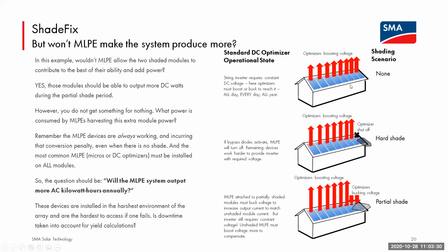So for non-shaded arrays, you would say, well, okay, Rob, I guess you've proved to me that traditional optimizers are not needed. But here you have a hard shaded situation. So in a hard shaded situation, that optimizer, again, cannot magically make power from a module that's not giving it any power. So this is showing that optimizer really shuts off. So there's no power from the module to power it up. So it bypasses over just like it would if it wasn't there, because we have bypass diodes. But what happens to the rest of those optimizers? They actually have to boost the voltage because they just lost 30 volts to make the inverter happy. And again, that's running those optimizers in basically a cycling state. For long-term reliability, that's a concern.